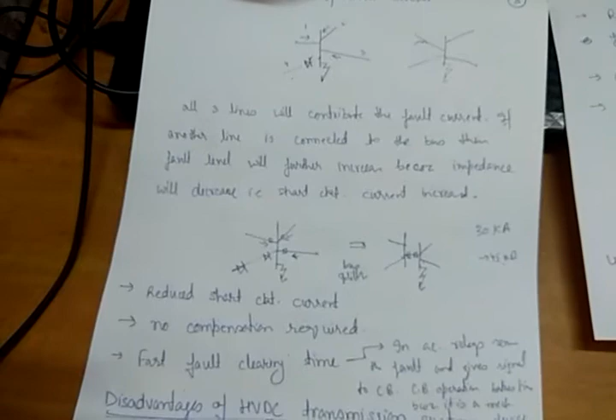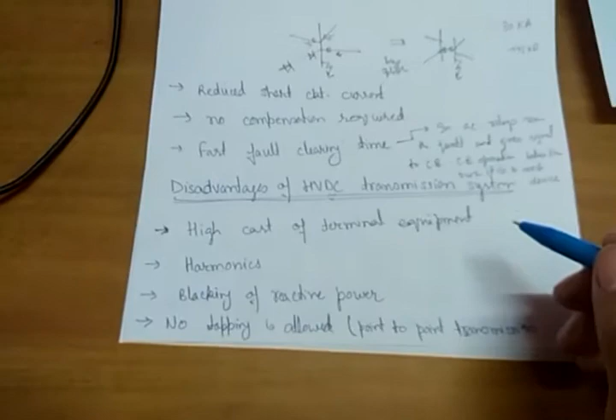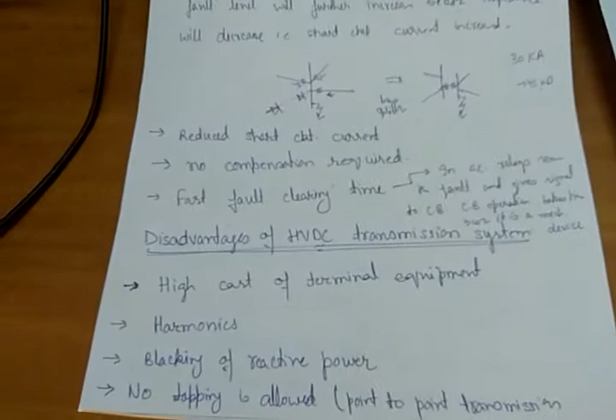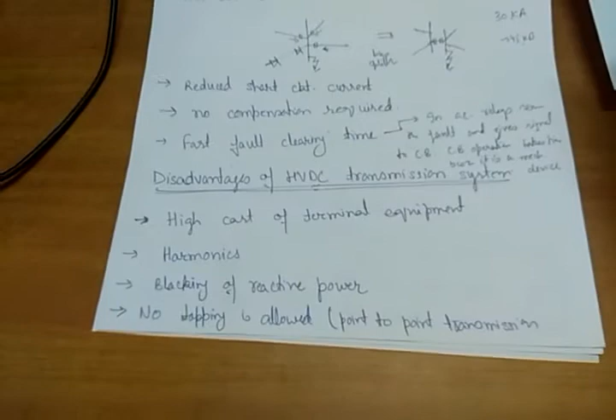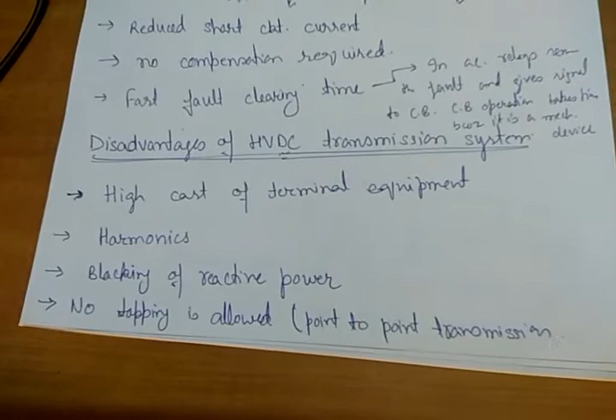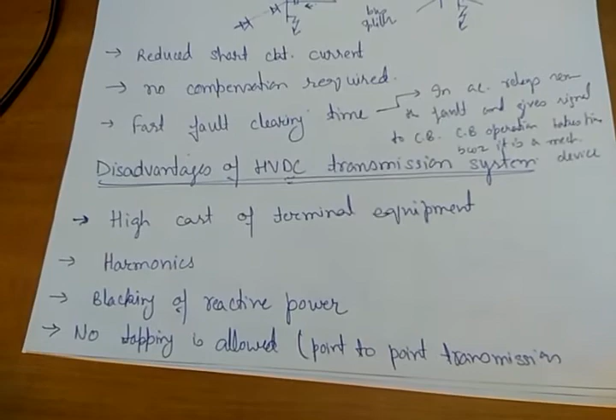Next, let us discuss some of the disadvantages of HVDC transmission. Though it has certain advantages, it has certain disadvantages as well. The first disadvantage of the HVDC transmission system is that the cost of the terminal equipment is high. Though it is cheaper for longer distances, the cost of the terminal equipment, meaning the equipment used at the substations, like the converters, converter transformers, and harmonic filters, is high. It increases the cost.